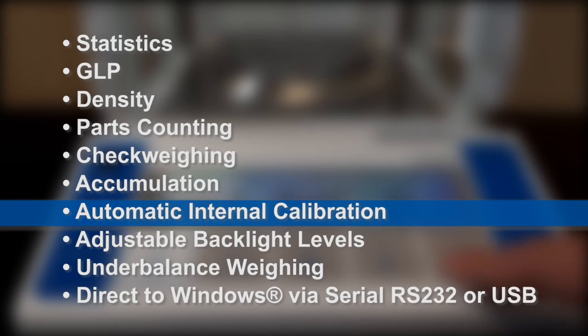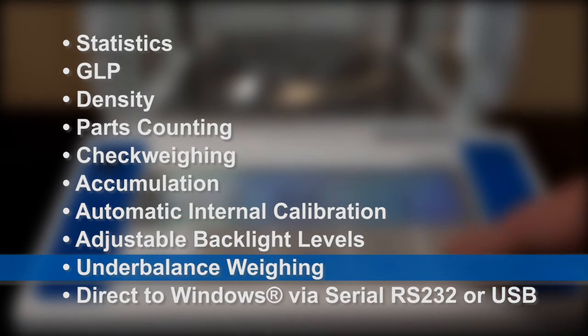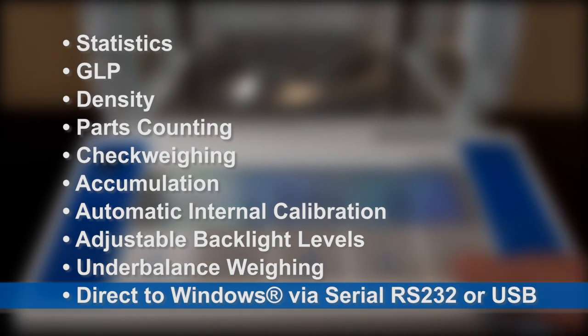Additional features include automatic internal calibration, adjustable backlight levels, under-balance weighing, and direct to Windows connectivity via serial RS-232 or USB.